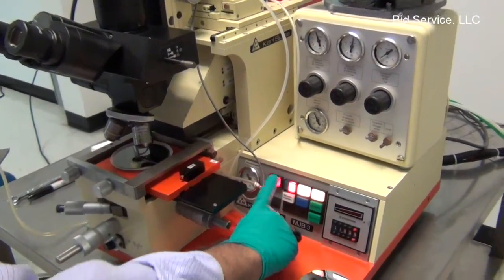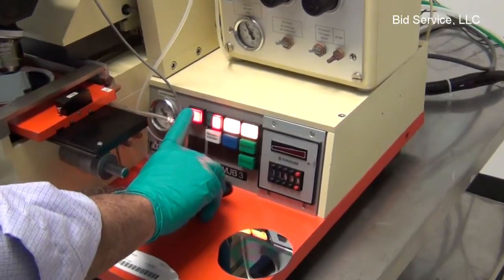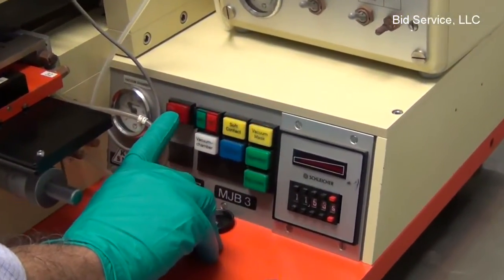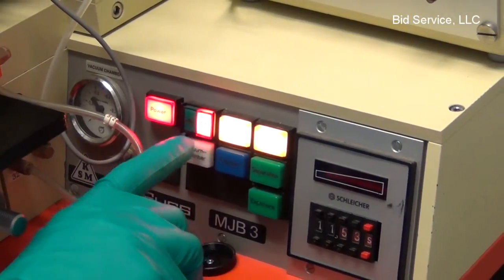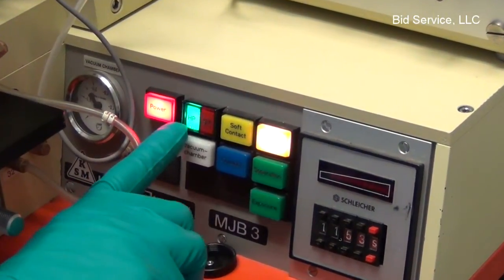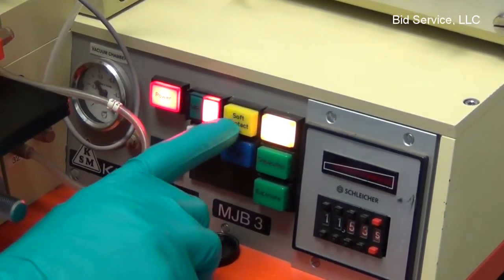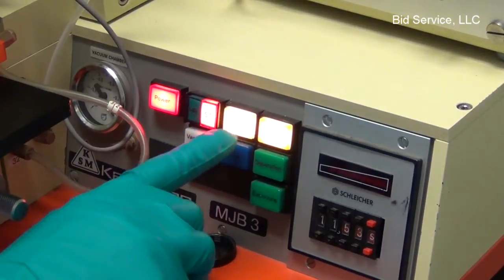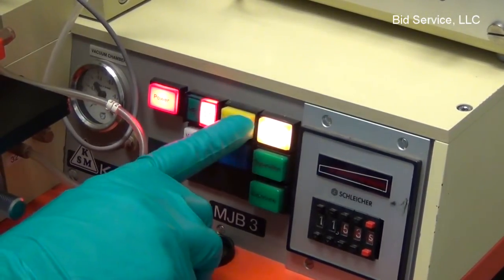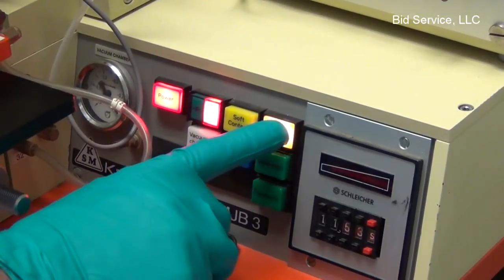The system controls over here: the power switch to turn on and turn off the system. And the switch here is for selecting the mode, either HP mode or standard mode. And there is a button here to choose in standard mode either soft contact, or when this light is not on, it is standard mode hard contact.